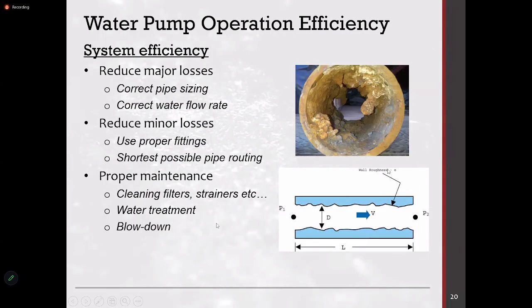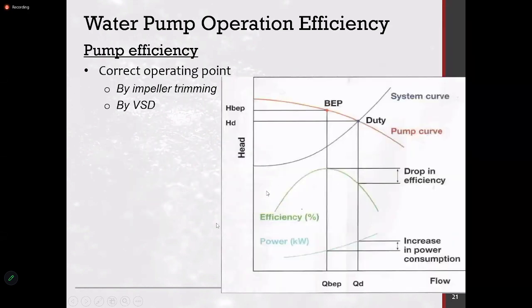Then water treatment is the other key where something like this could happen if the water is very bad and if you are pumping, like we discussed, the hot water systems. If the hardness is high, then there'll be deposits of calcium carbonate and other dissolved solids in the piping system and it will increase the friction losses. Blowdown is something with regard to steam systems and boiler systems, which we have discussed.